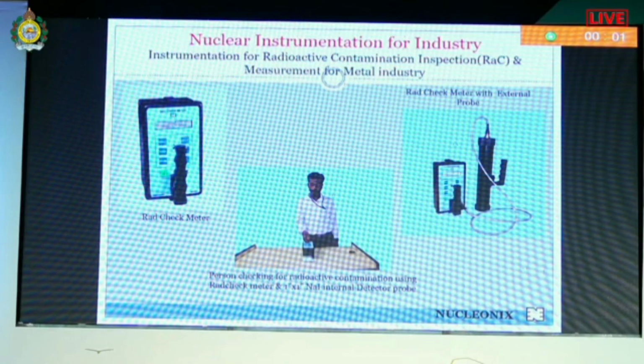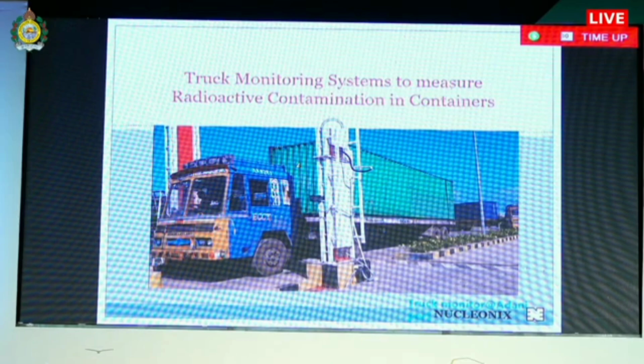For the recycled steel industry, which was facing export rejections a couple of decades back, we were the first to develop this package of instruments. Rad check meter is one. It is basically a micro survey meter that sniffs. When it touches the component, it attenuates the natural background. If the attenuation is more than 15%, we say the component is clean. It comes with external probe and internal probe. And there's a truck monitoring system for containers carrying metal scrap. In all, we have supplied to about 8 to 10 systems.